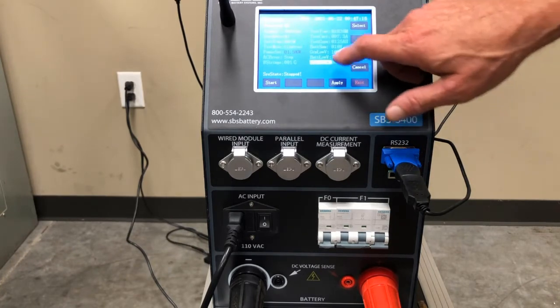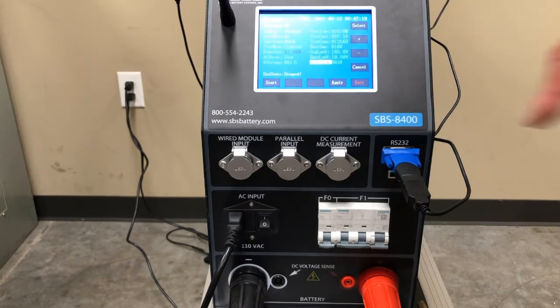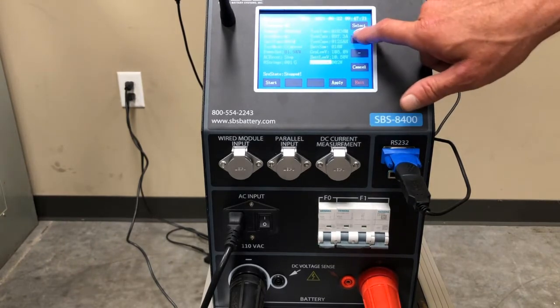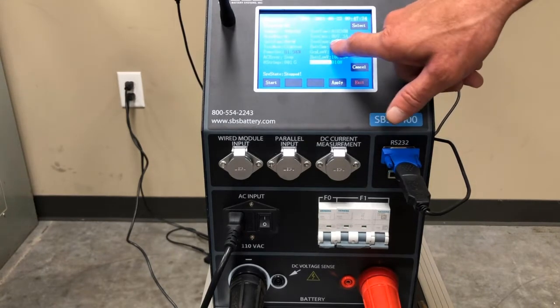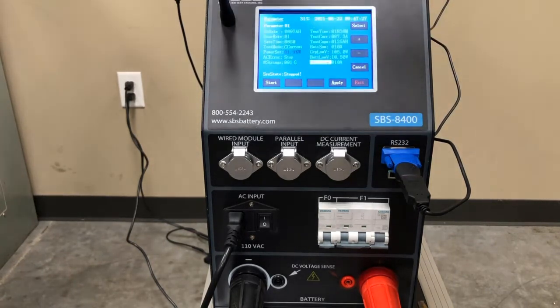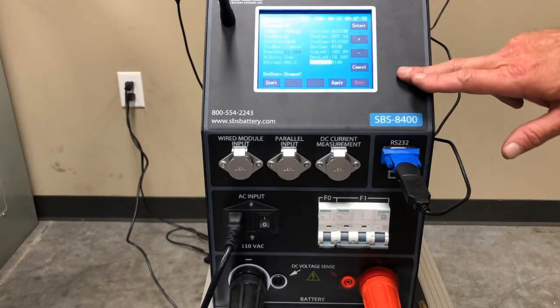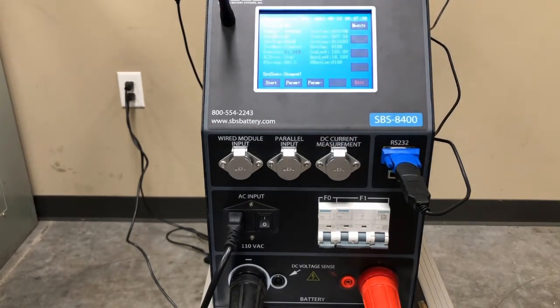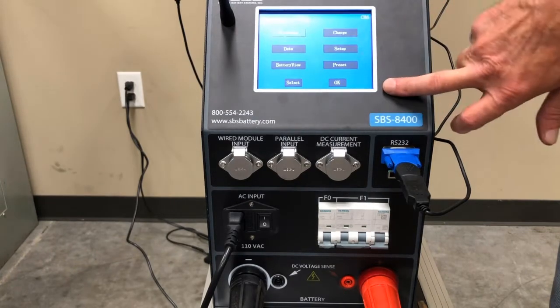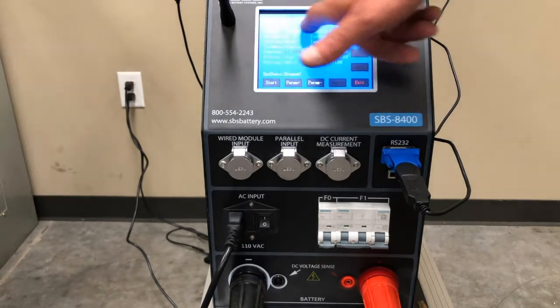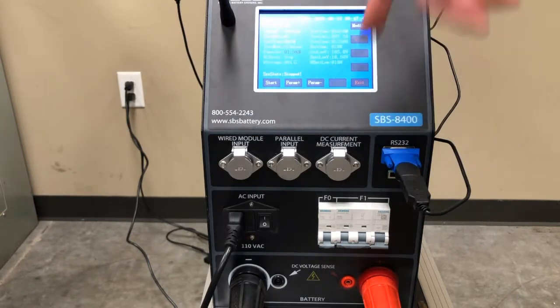Right. So because we're not using the wireless modules for this test, I'm going to set number of battery lows all the way up to 10, equal to the number of batteries that we're testing. So it's going to ignore us not having the wireless modules connected to the system. Now once I get all of these parameters set, I'm going to hit the apply button. It's going to overwrite that preset. So now if I go back out and go back into discharge, all those values that I just programmed show up as preset number 1. And they're going to stay in memory as preset 1 until I modify or write over the top of them.